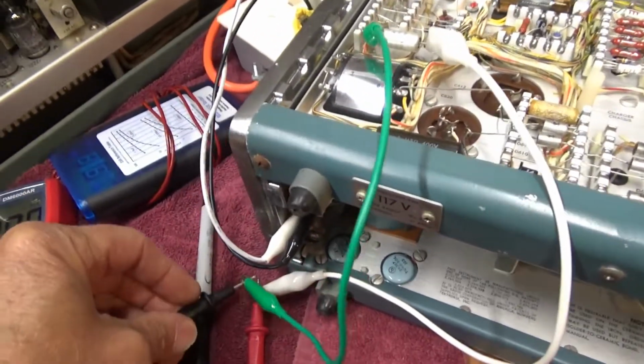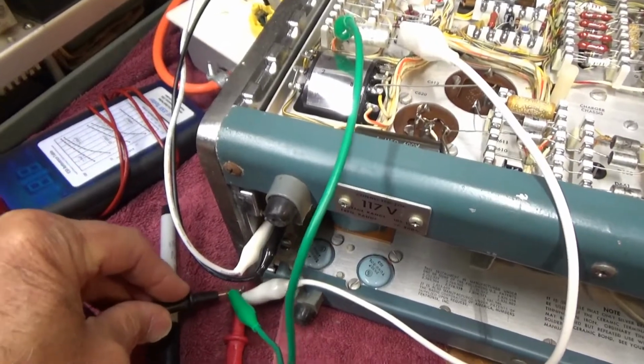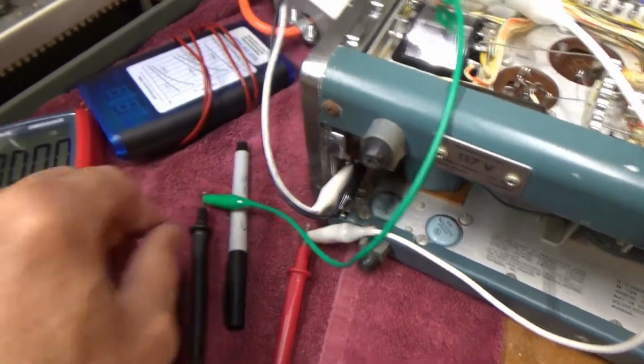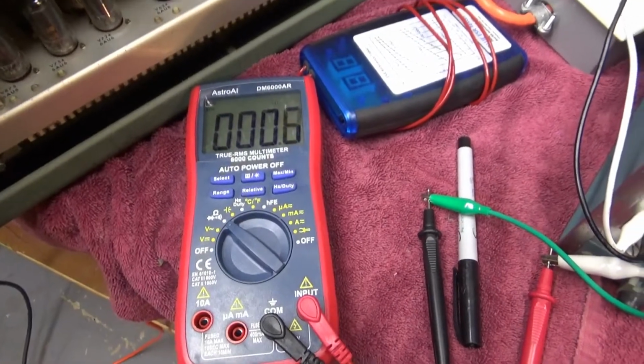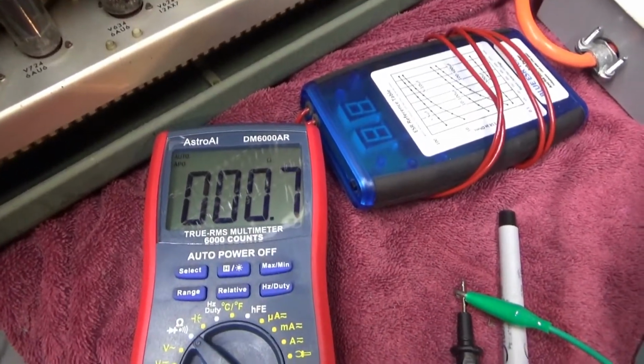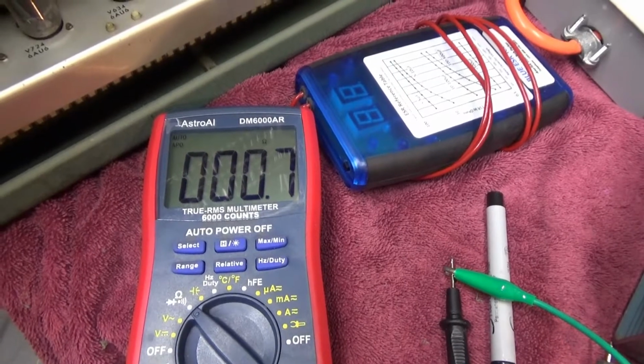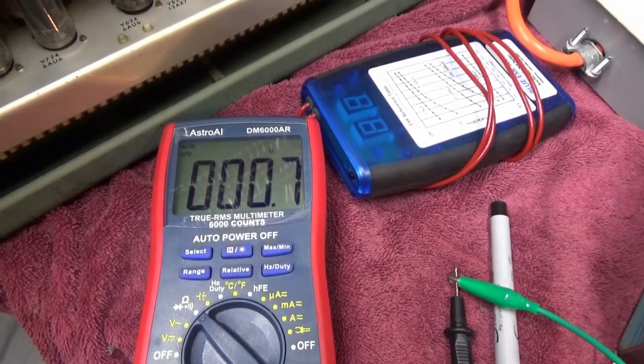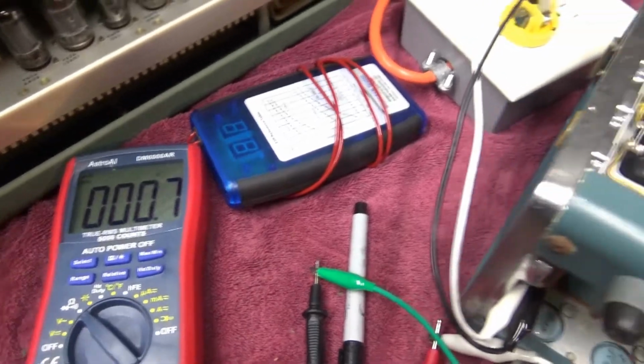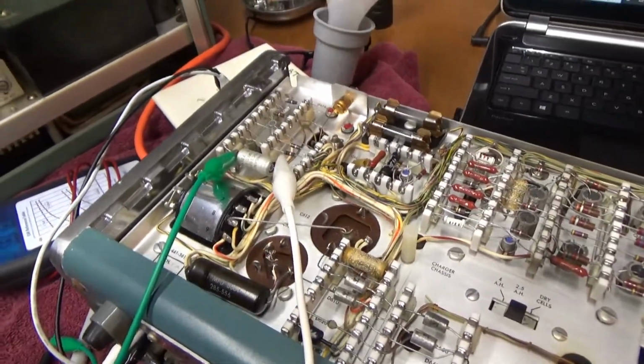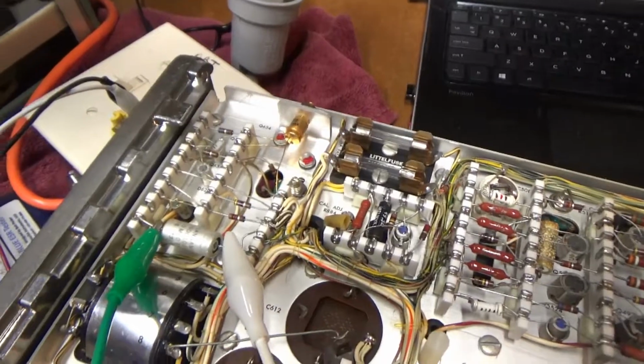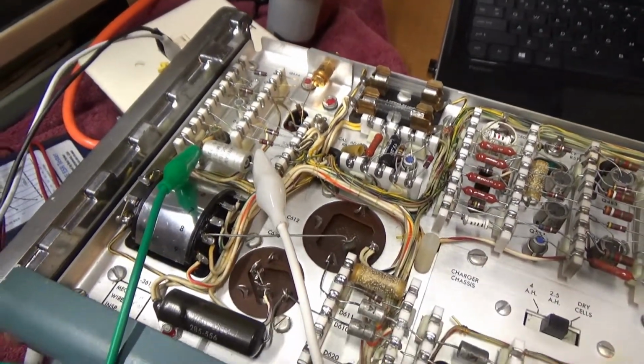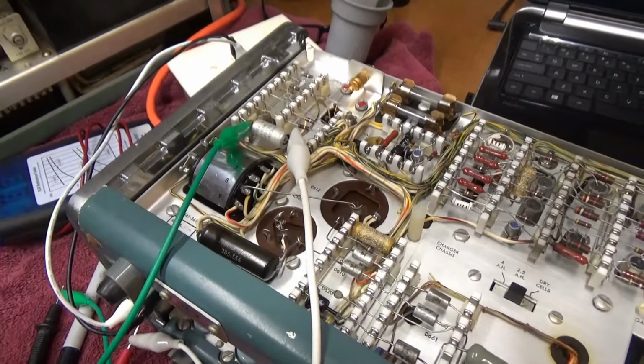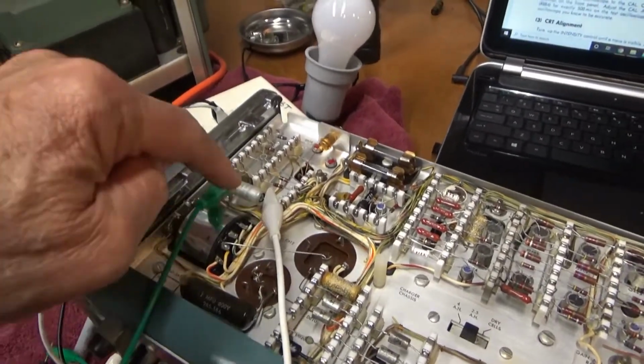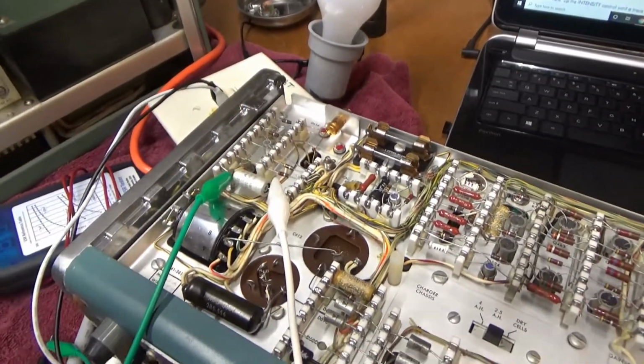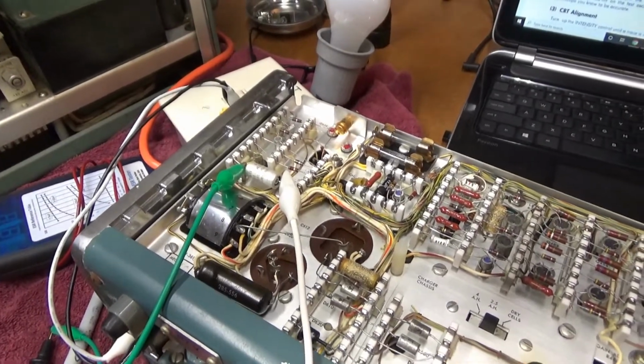So here, let me short out that capacitor to drain any voltage out of it. Let's check the resistance across it. We're getting about 7/10 of an ohm. I was getting as low as 4 or 5/10 of an ohm. So I think that capacitor is shorted, or something else in the circuit is shorted. It's changing slightly because the voltage did go up from about 1 volt to 1.7 or whatever. So I think I'll pull that thing out of the circuit and see if that solves the problem.